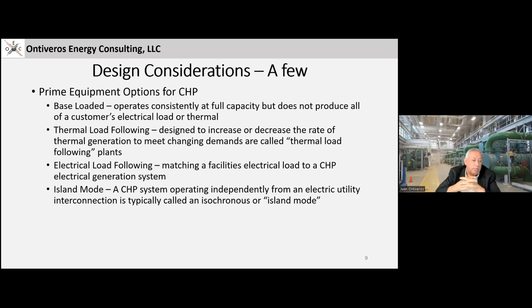Just some quick considerations about CHP. Now, do you want to do base loaded? Basically, you're operating consistently at full capacity, but you don't produce all of the load, whether it's electrical or thermal. Thermal load following is designed to increase or decrease the rate of thermal generation to meet the demands of the plant. Electrical load following is matching a facility's load to a CHP system. So that's another option. And then you want to go island mode.